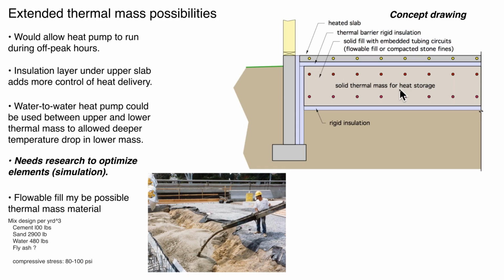And the reason I'm putting insulation between the upper slab and the lower slab is we have thermal separation. If we don't have that insulation there and we drive this thermal mass up to an elevated temperature, we could have overheating, and we have no way to control that. But with a layer of insulation in between, we could do things like just close the zone valve or shut off the circulator, so we aren't allowing the heat that's stored in the solid thermal mass to just keep flowing up through that upper floor.